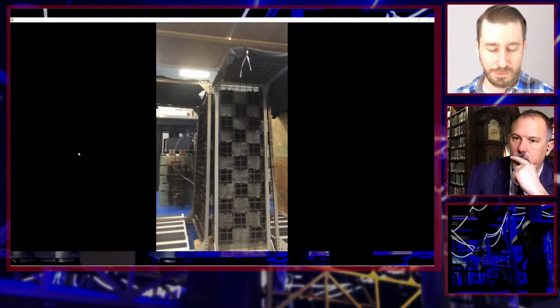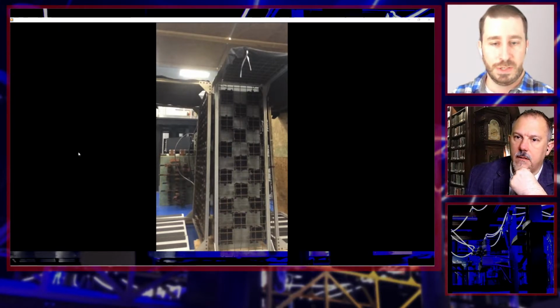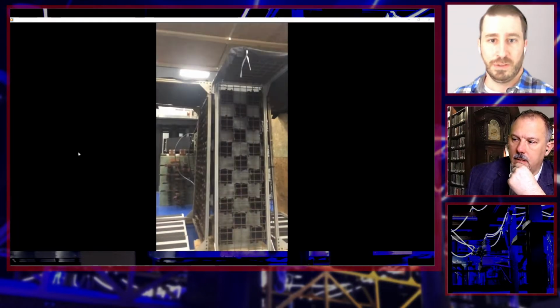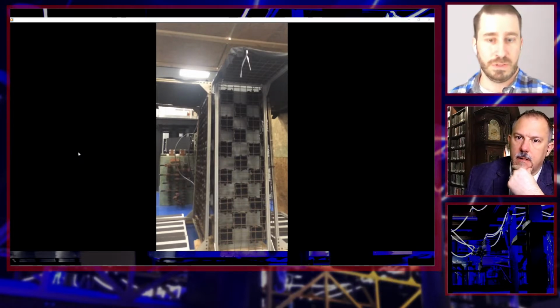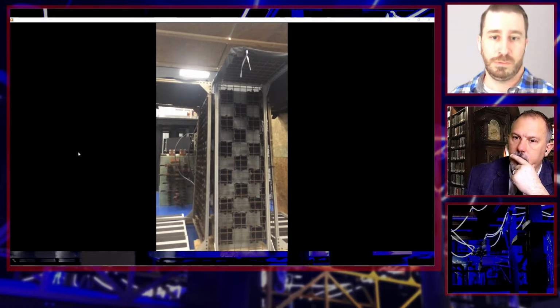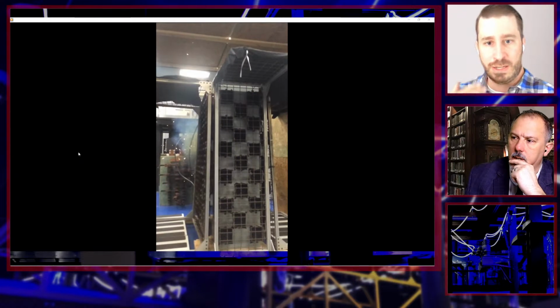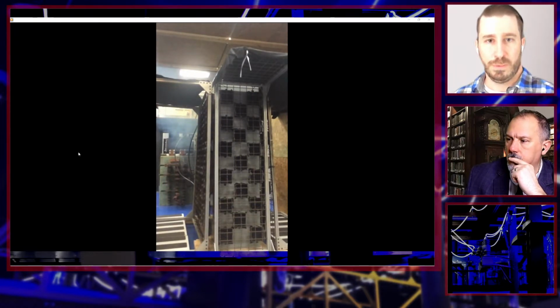And they're about a 4 by 4 inch square. And as you can see, they're very tightly configured around the equipment. So basically, this is trying to maximize it: if there's anything coming out of the equipment and a hot flame or ember catches, ignites those, that's going to catch and identify that as a fail. Obviously, in this particular situation, it was all good. Additionally, the test stand is located about 4 inches away from the equipment.